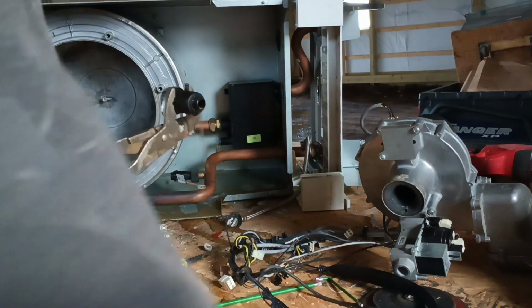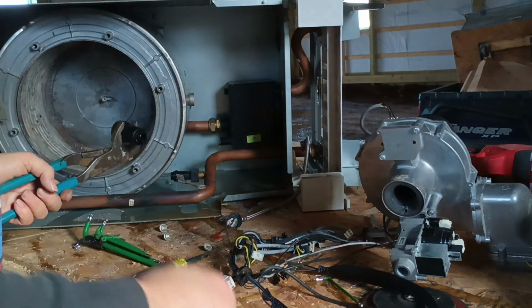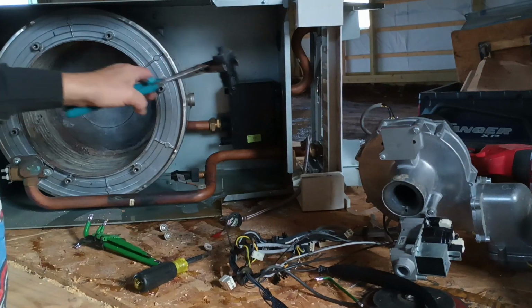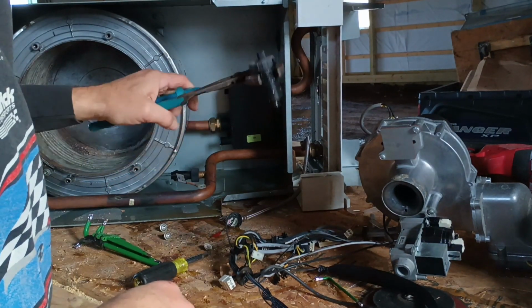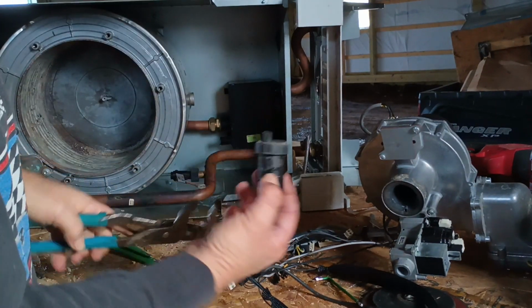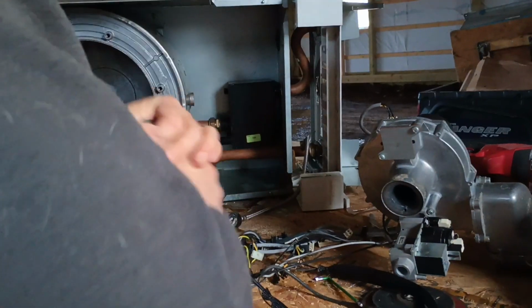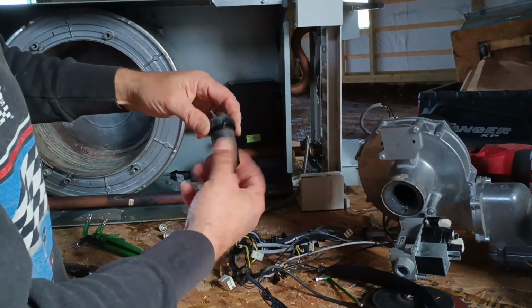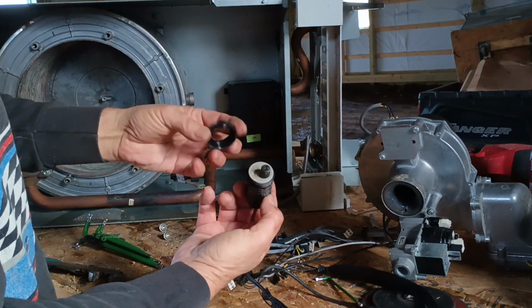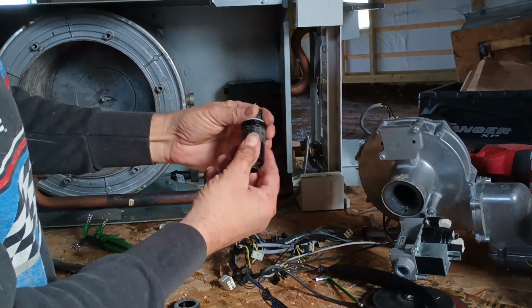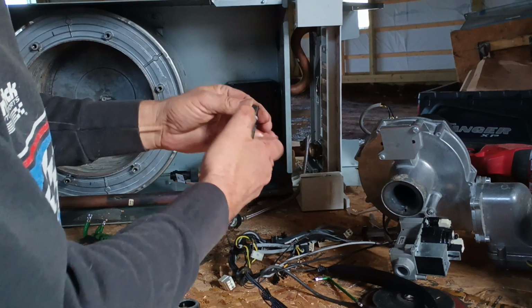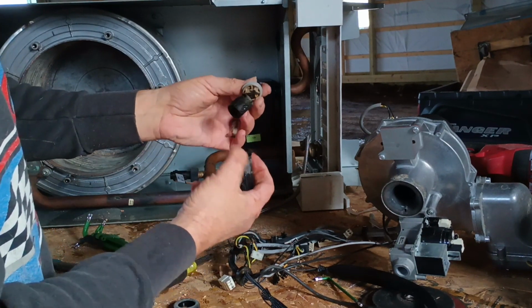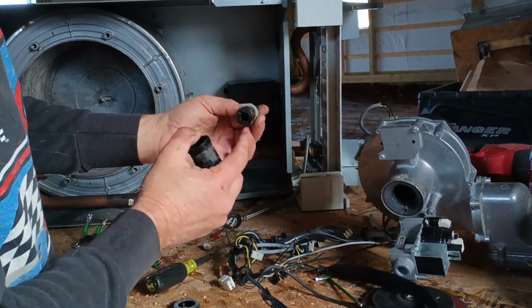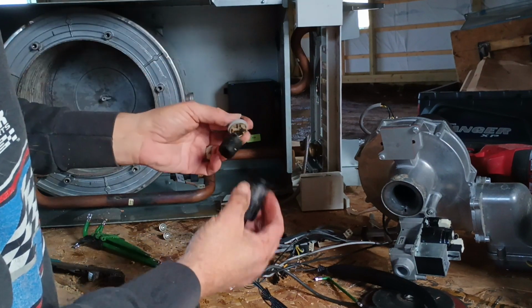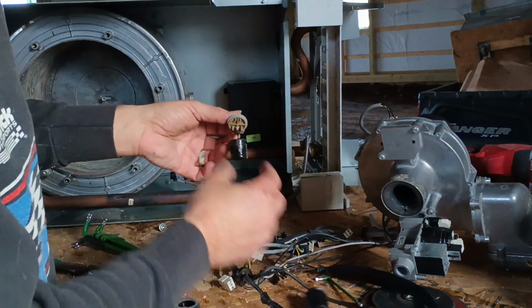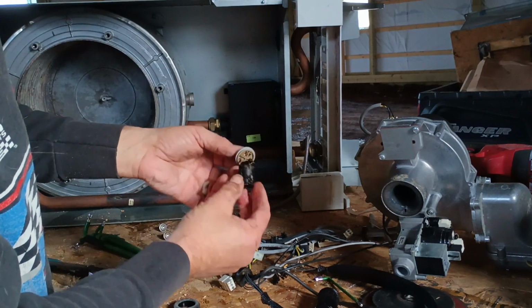And so we still have some glycol left in here. So we're proceeding to dump that all over the place. Little auto float. These things are just a needle seat and an air vent. So you can pop these apart and service them. Really doesn't look too bad on the water side. You can smell the antifreeze, most likely propylene glycol.